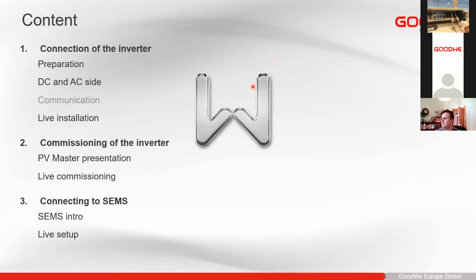Okay, so now we have the AC connected, the PE is connected, and now we will go ahead to the DC side. And on the DC side here, you just need to remove this, make sure that it's on off, and then after you have taken your proper DC cables and crimped the MC4 connectors on, make sure that you first measure the polarity. So you're connecting plus to plus and minus to minus, and then you just need to plug them in.